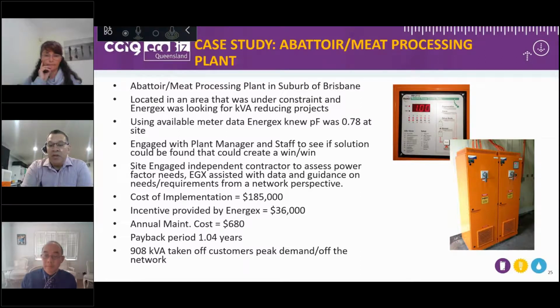So you can see on the pictures on the right-hand side there, if anyone's wondering what power factor correction equipment looks like, mostly from the outside they look like big, nice orange boxes. But then you see a close-up is often a little panel that tells you where the power factor is for the particular circuit that equipment is working on. As you can see on the example here, it's sitting on 1.00. So we've got unity power factor.